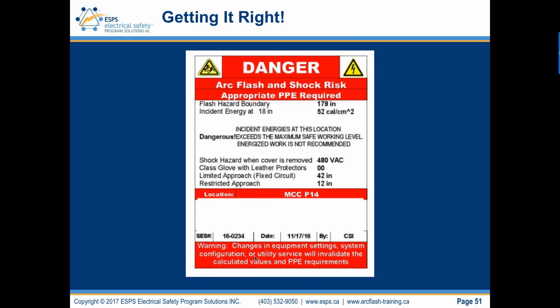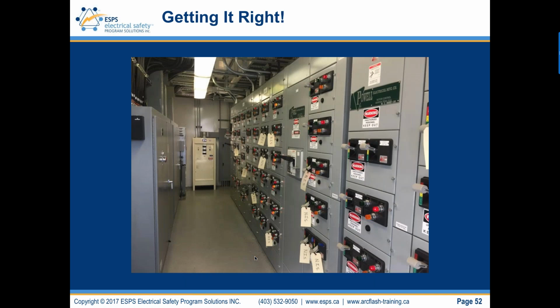This label again: incident energy at this location exceeds the max safe working level. Energized work is not recommended. 52 calories. So 52 calories, it's greater than 40, right? Dangerous. Again, those words shouldn't be used. There should be information provided that clarifies this issue.